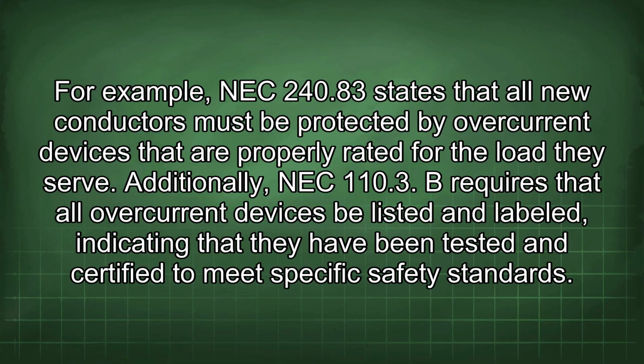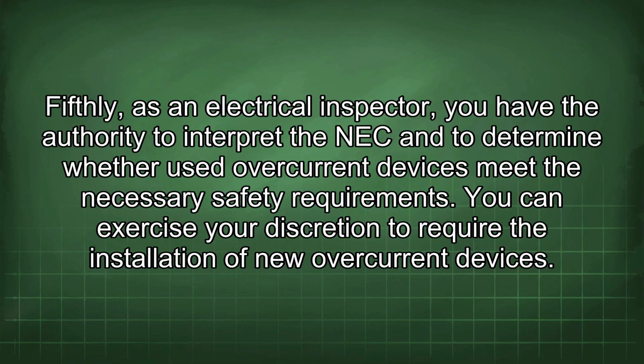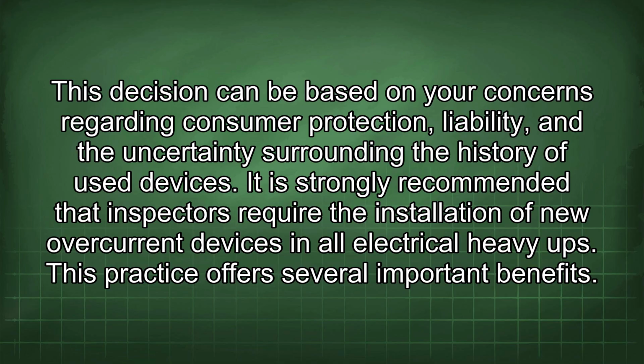Fifthly, as an electrical inspector, you have the authority to interpret the NEC and to determine whether used overcurrent devices meet the necessary safety requirements. You can exercise your discretion to require the installation of new overcurrent devices. This decision can be based on your concerns regarding consumer protection, liability, and the uncertainty surrounding the history of used devices. It is strongly recommended that inspectors require the installation of new overcurrent devices in all electrical heavy-ups.